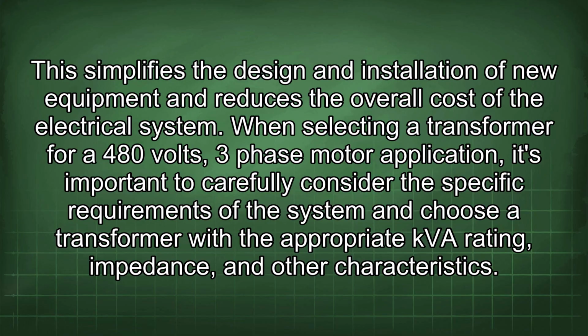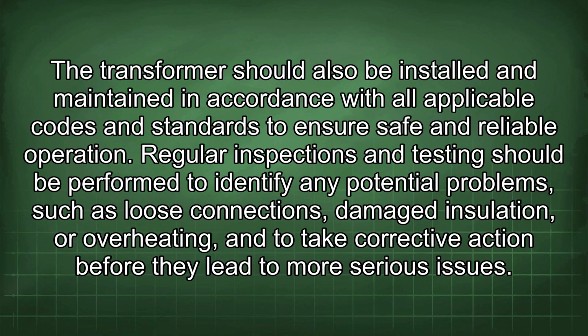When selecting a transformer for a 480 volts 3-phase motor application, it's important to carefully consider the specific requirements of the system and choose a transformer with the appropriate kVA rating, impedance, and other characteristics. The transformer should also be installed and maintained in accordance with all applicable codes and standards to ensure safe and reliable operation. Regular inspections and testing should be performed to identify any potential problems such as loose connections, damaged insulation, or overheating, and to take corrective action before they lead to more serious issues.